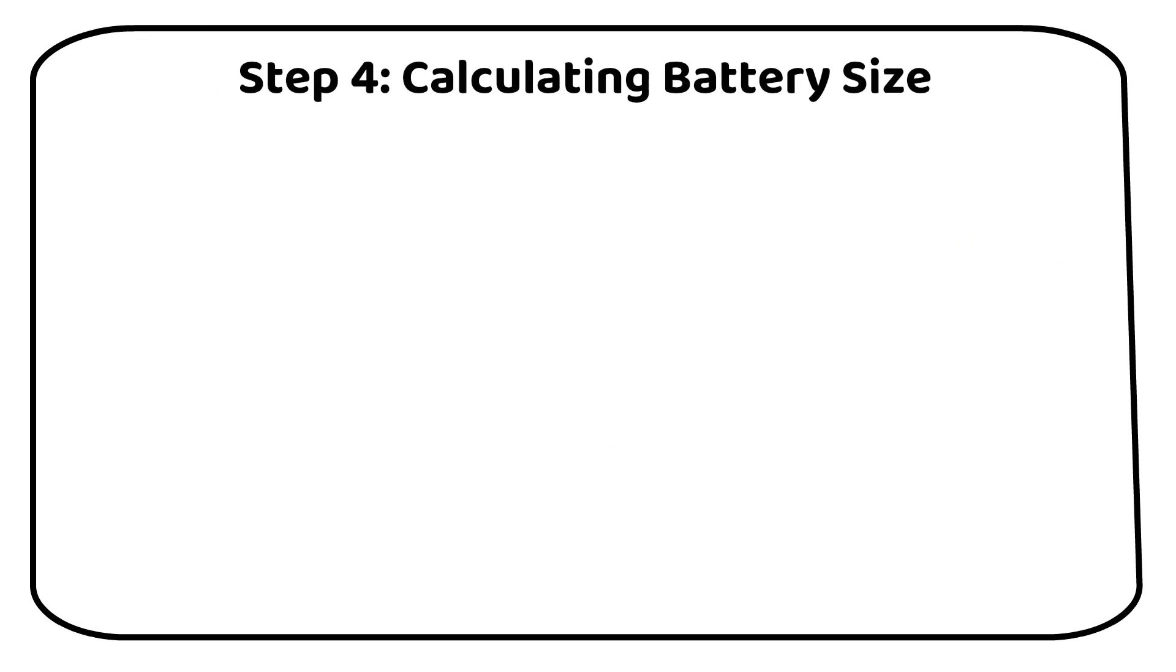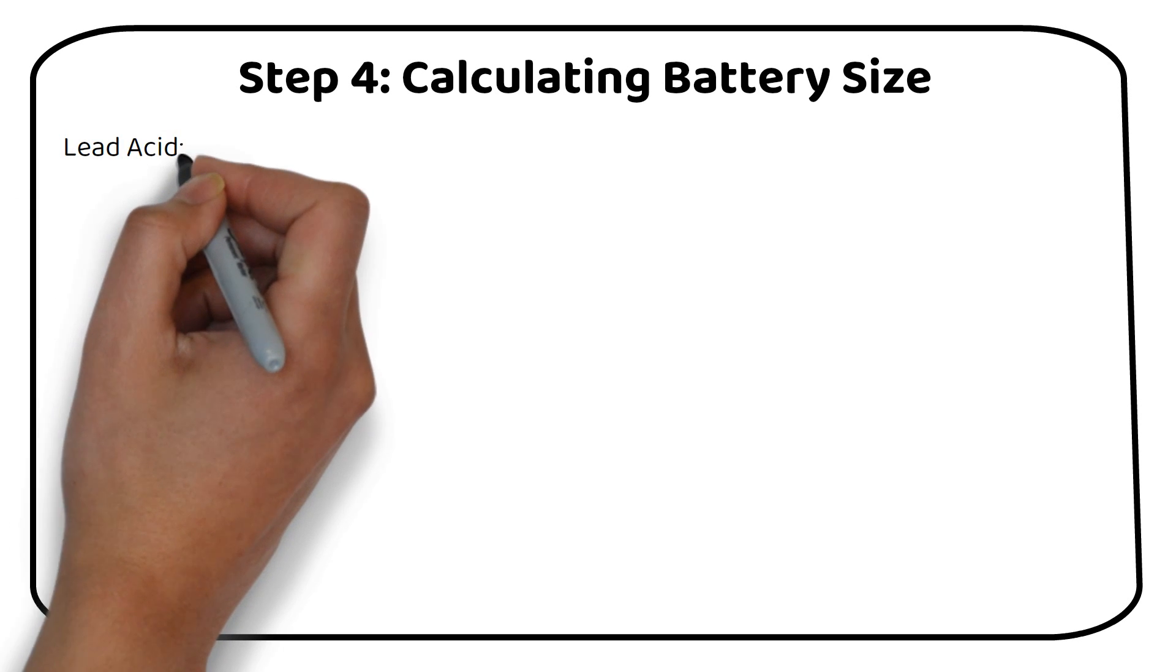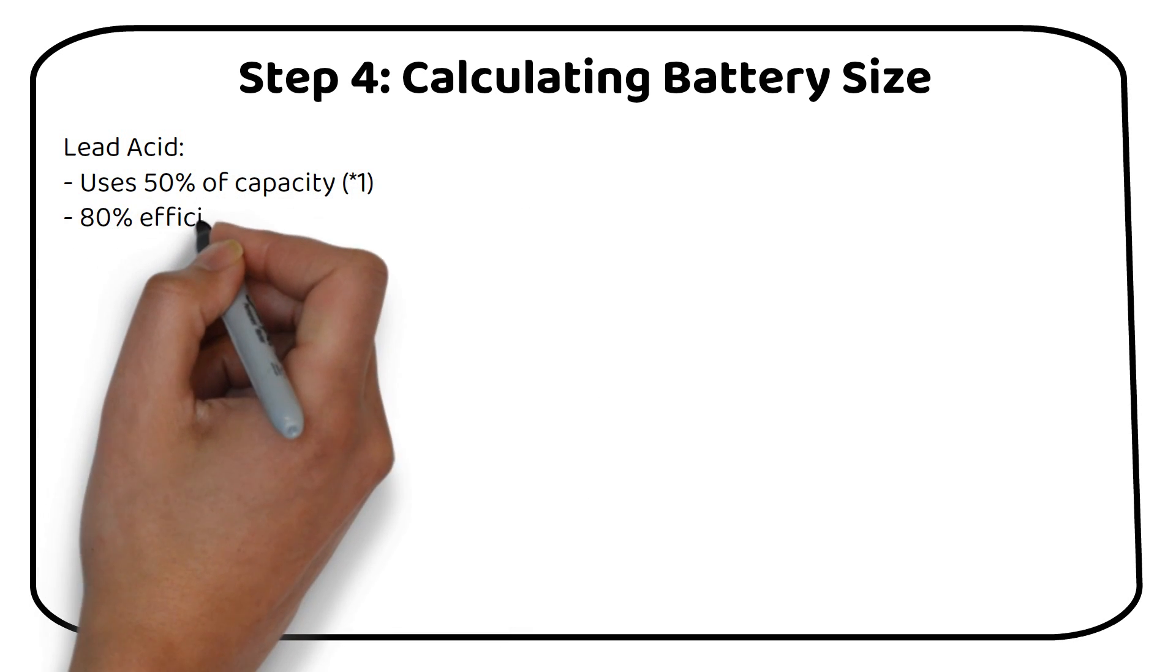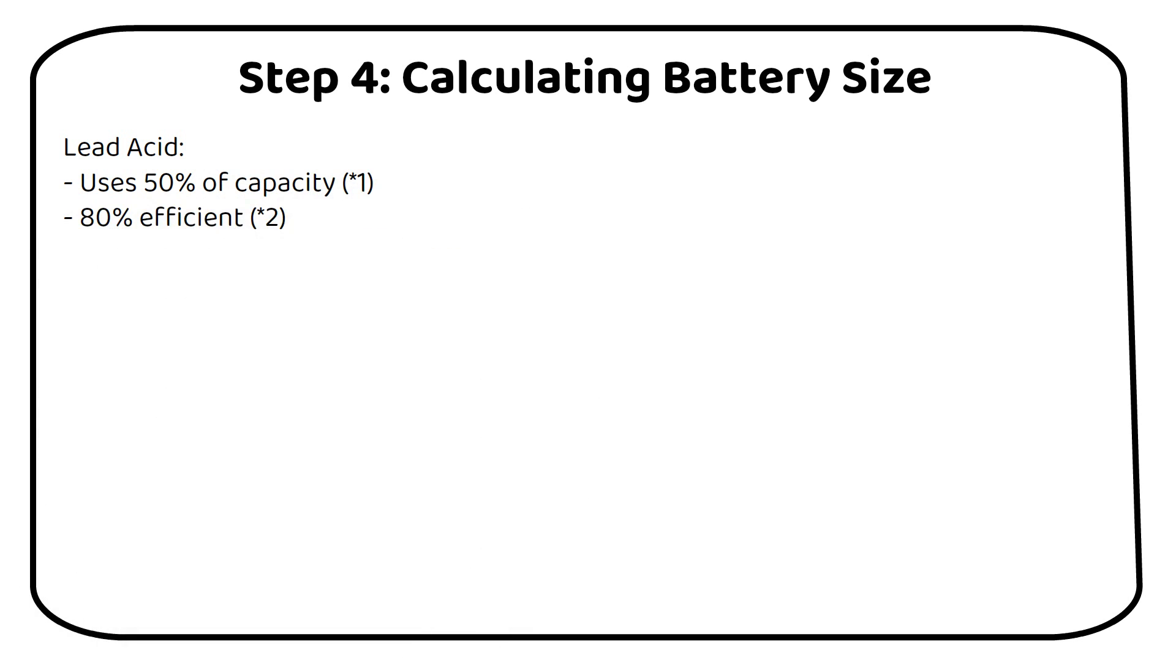Step 4. Calculating battery size. Now, let's dive into some calculations for both lead acid and lithium batteries. There are two key factors to consider in this calculation. For lead acid batteries, remember that you can only use about 50% of their capacity. And they have an energy conversion efficiency of around 80%. This means that for every 100Wh you put into the battery, you would get about 80Wh of usable power.